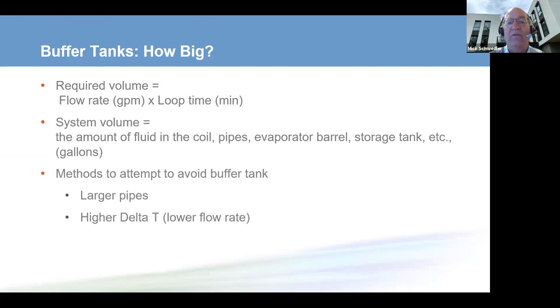One low-cost way, if these values are close to one another, is to make your pipes and the manifolds a little bit bigger. Not your bypass pipe, but the manifolds a little bit bigger to increase the water volume in them. You could also increase the delta T, because since tons is equal to GPM times delta T divided by 24 for water, if you increase the delta T, you decrease the flow rate, the GPM, and when you multiply that lower flow rate times the loop time, you might now meet the system volume requirements.